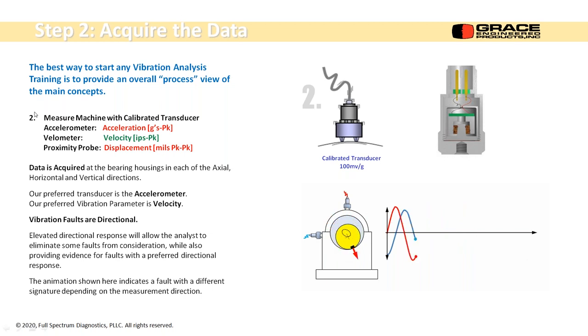Where we go with this one, we're going to measure the machine with a calibrated transducer. Typically, it's an accelerometer. It gives us acceleration. Accelerometers are the best transducer to use, but acceleration is not the best unit to use because it has a problem we'll talk about on Thursday with some of the basics of vibration. It changes amplitude with speed or with frequency. So we have a problem with the acceleration parameter and the displacement parameter.